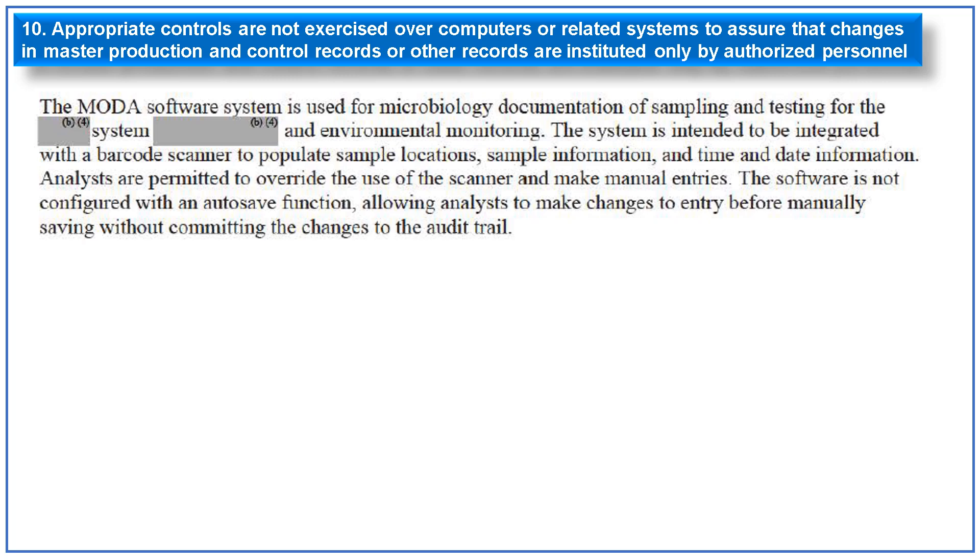The tenth and last observation is related to appropriate controls not being exercised over computers or related systems. A MODA software used in the microbiology laboratory to document sampling, testing, and environmental monitoring is intended to be integrated with a barcode scanner to populate sampling locations, sample information, time, and date. However, analysts are permitted to override the scanner and make manual entries. The software is not configured with an autosave function, allowing analysts to make changes to entries before manually saving without committing the change to the audit trail.